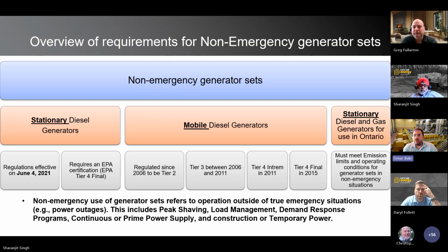Then we move to the Ontario emissions regulations. In Ontario, both diesel and gas generators must comply with emission limits and operating conditions for non-emergency use. Ontario regulations regulate stationary generator sets, but do not regulate mobile generator sets in non-emergency use. This makes non-emergency projects more complex from a regulatory and design perspective, where we may need extra after treatment, because Ontario requires NOx levels for non-emergency stationary generators to be 0.4 gram NOx, which is actually more stringent than the Tier 4 final requirements. So we have to keep in mind that Ontario, for non-emergency use stationary engines, has more stringent requirements than the federal level.